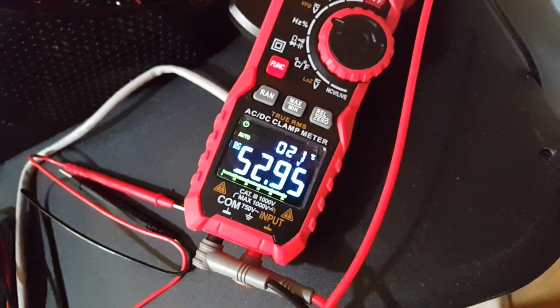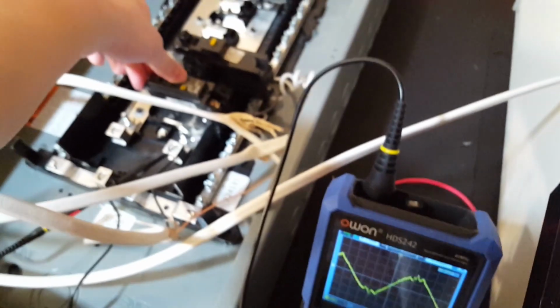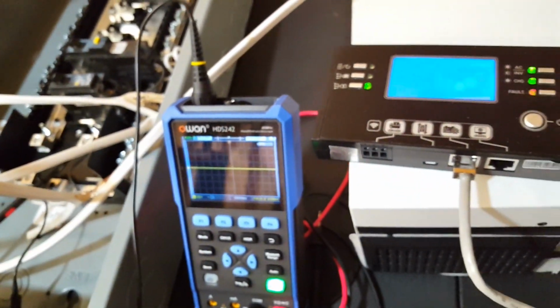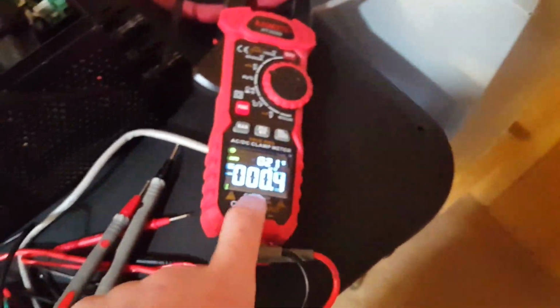Alright, the battery voltage right now is showing 52.9, but I want to check that. Pack voltage 52.9. Okay, very accurate. Let's check again under load with the air compressor. Ooh, it failed to start. Couldn't do it. I didn't have this on inrush mode, so I don't know what the amps was, but the point is that failed. Turn on AC input.